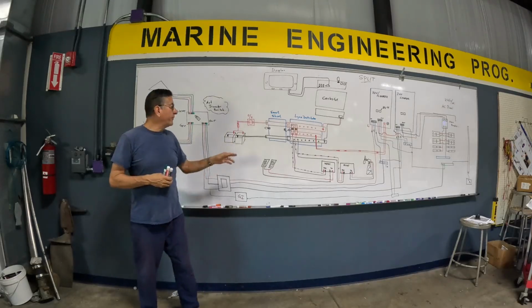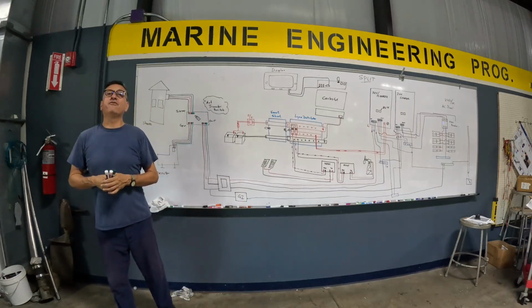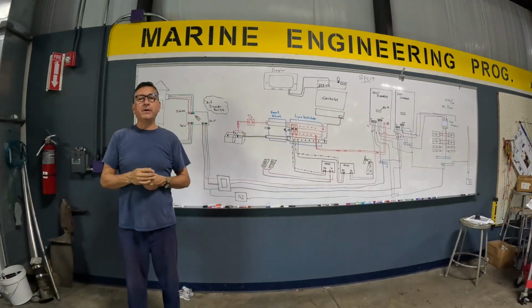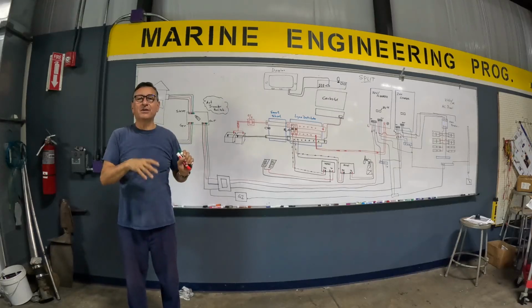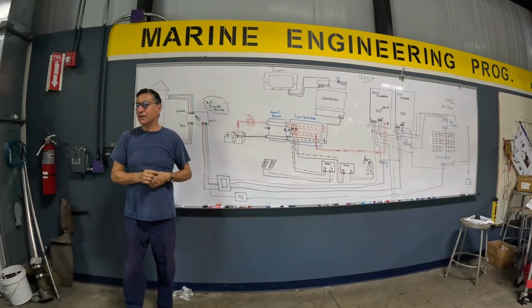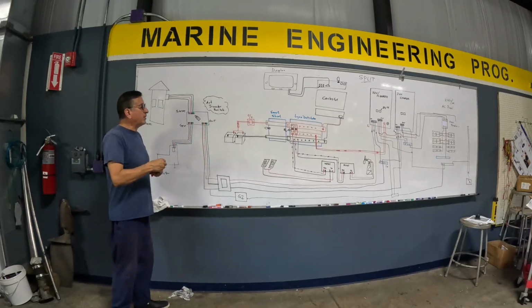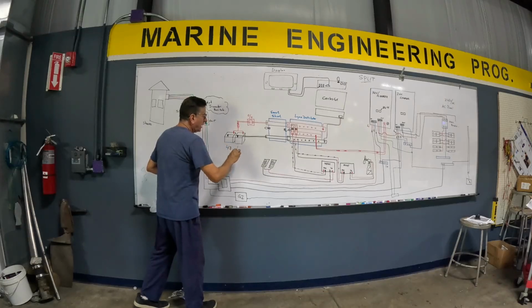decision whether I configure the batteries in 12 volts, in 24 volts, or in 48 volts. What is better? Higher voltage is better because I need to collect fewer amps to produce the same power. You remember we did that exercise a couple of times. All right. Suppose that I configure this panel in 48 volts and some amps.